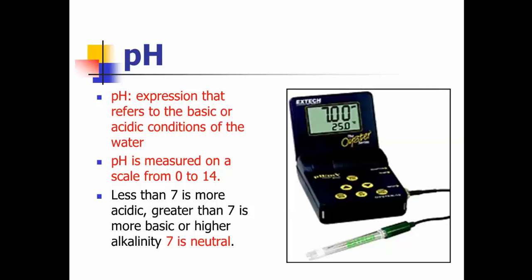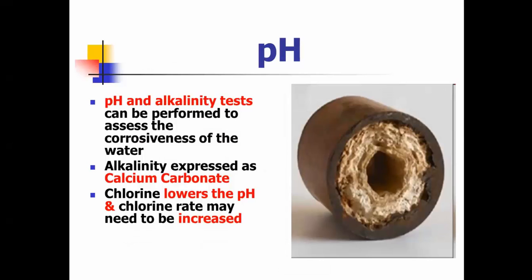Now pH, that's an expression that refers to the basic or acidic conditions of the water system. It's measured from 0 to 14, and 7 is neutral. So below 7 is acidic or aggressive, and above 7 causes scaling on the pipes. The pH alkalinity test.